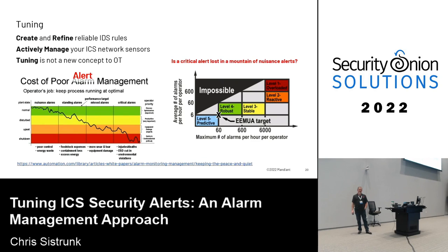But it tells you what happens if you have not tuned your system. Basically, nuisance alarms become standing alarms. Standing alarms become performance target missed alarms. Then you're getting into wear and tear of machinery, equipment damage. And if you're overwhelmed with so many alarms you don't know what to do with, you're missing critical alarms. You're going to have injuries and possibly deaths, emergency shutdown, or environmental violations. If you can't manage your security alerts the same way control system engineers manage the alarm system.